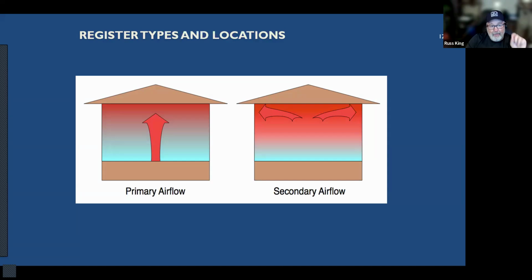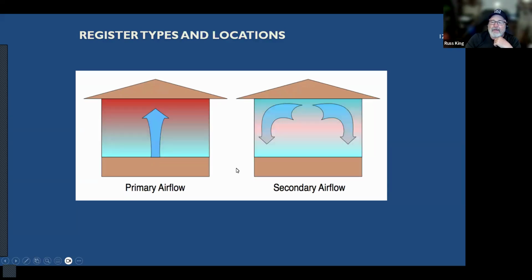You want mixing. The most important thing that a supply register can do is mix the air. And it mixes the air by having good airflow and being pointed in the right direction. When I design systems, and when I teach classes, my general rule of thumb is to blow the air the opposite direction that it wants to go. So if hot air wants to rise, blow it down. If cold air wants to fall, blow it up. If air wants to leave a room, blow it into the room. And that promotes mixing. If air is crashing into itself while it's trying to leave the room, you get better mixing that way. So there's just some diagrams for that.